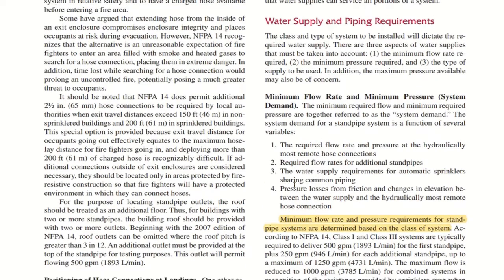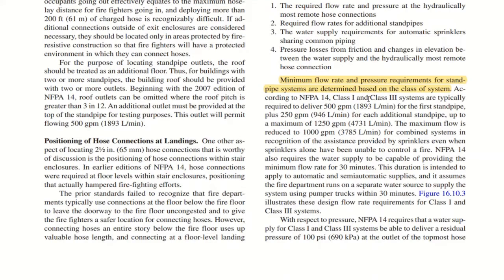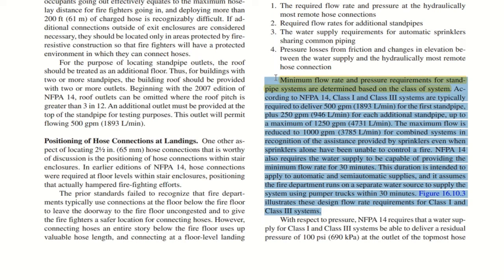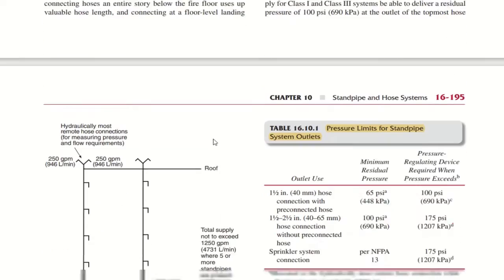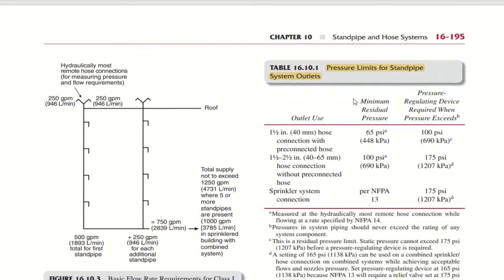Water supply and piping arrangements. Minimum flow rate and pressure requirements for standpipe systems are determined based on the class of system. This is an important paragraph. You just go through this. So for pressure limits for standpipe systems, they have mentioned 65 psi for 1.5 inch, and for 2.5 inch it is about 100 psi.